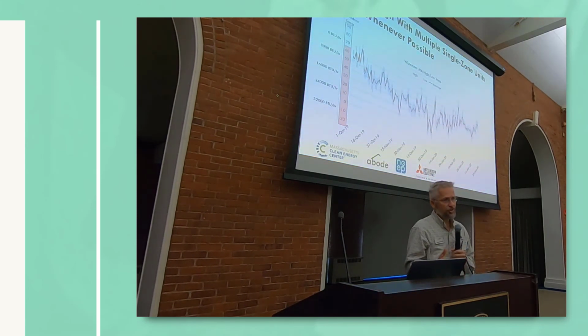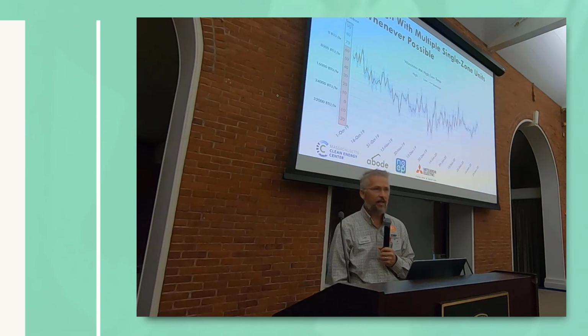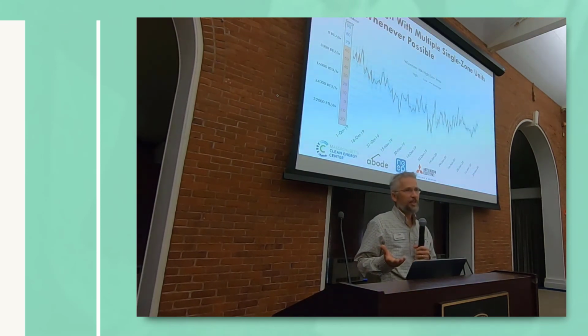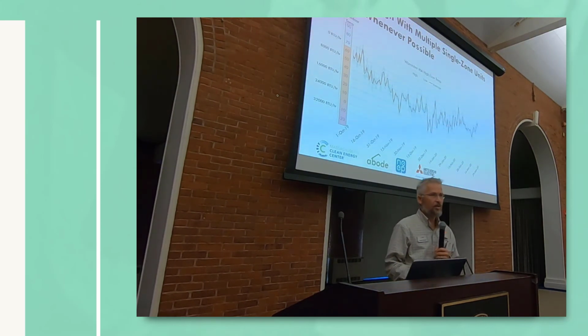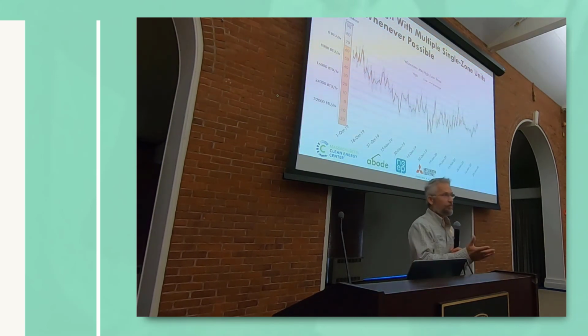Manual J is just really the first chapter. There's actually a manual S, for selecting the equipment. And that has a bunch of different guidance, and we get into that in some of the later slide decks. But you're not supposed to size the cooling equipment greater than 130% of whatever comes out of your manual J. And there's also rules about matching your cooling to your heating load that come with manual S. And then there's a manual D for sizing your ductwork.